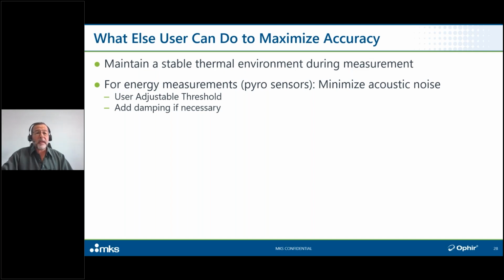But for energy measurements using pyro sensors, what's more important is that you minimize acoustic noise. Pyroelectric sensors will respond to acoustic pulses with the same physical mechanism by which they respond to laser pulses. So if there's noisy machinery in your building, the vibrations come up through the floor much more readily than through the air. If it is a potential problem, you'll possibly notice jumpy readings, false triggering. So you could do something as simple as add some damping between the mounting base of the sensor and the optical table to damp out those vibrations. Ophir pyroelectric sensors also have a user adjustable threshold, so you can hopefully find that Goldilocks level that'll keep the noise out but let your laser pulses in. So that's a nice feature to have there.